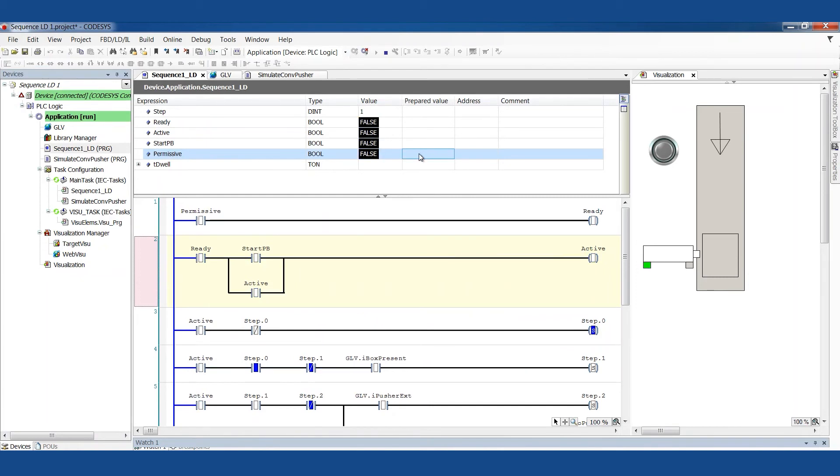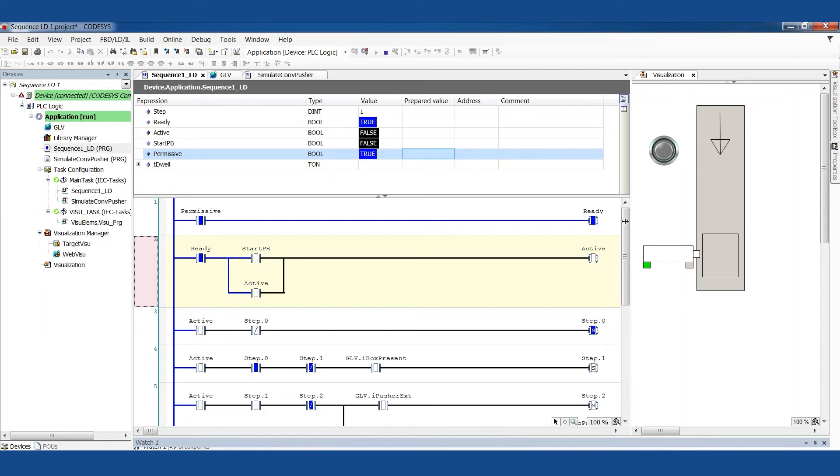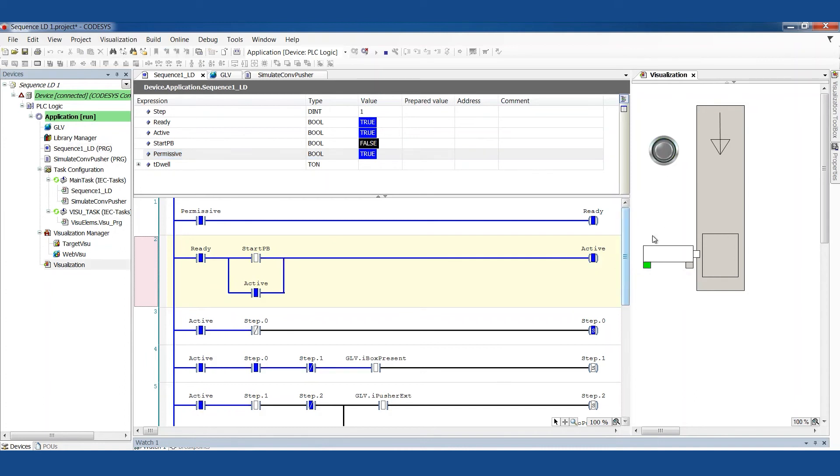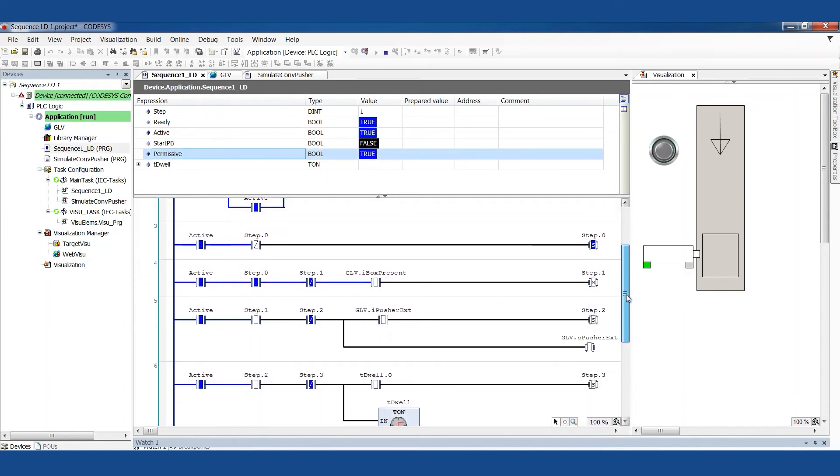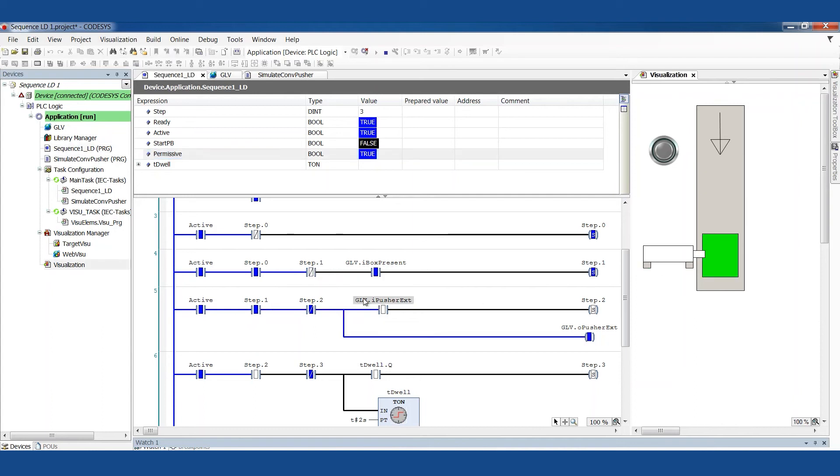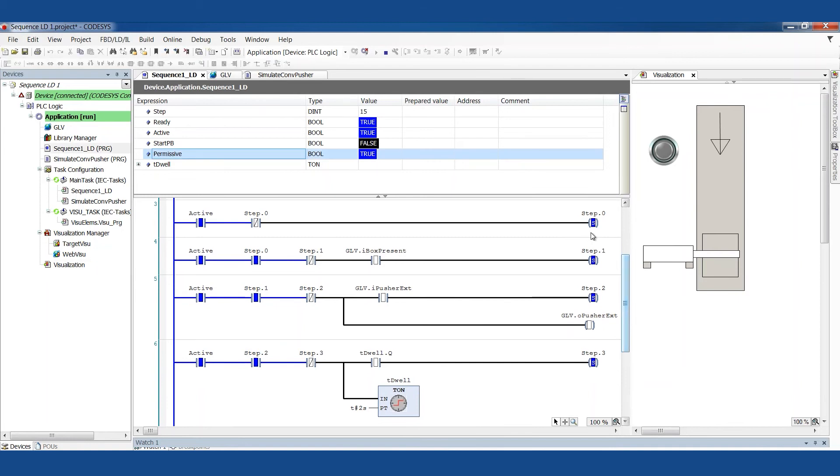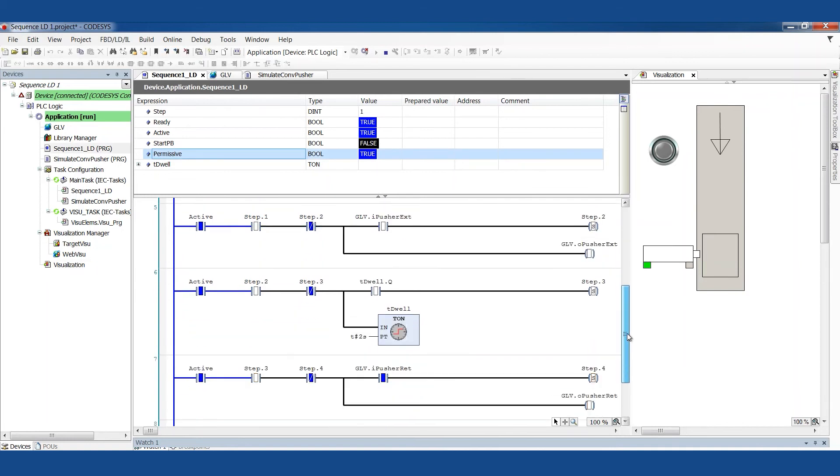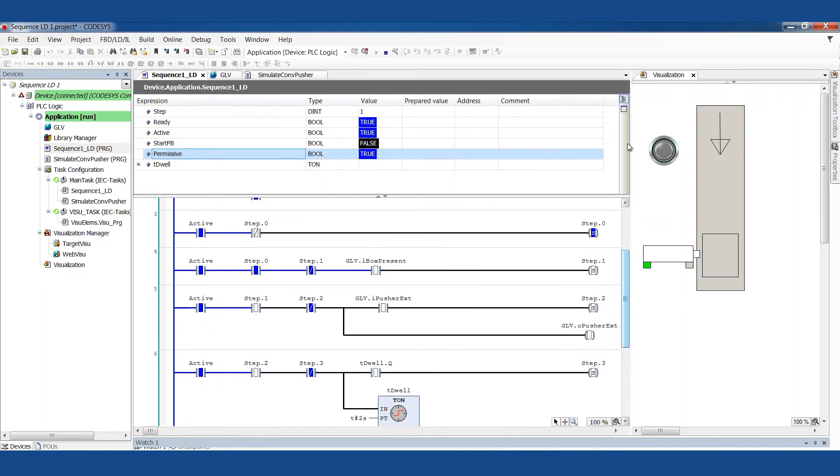I'm going to just reset this whole thing. Set my permissive to true. Again, that's guard doors are closed or e-stops are happy or we're in auto mode or whatever those permissives are. I see we're ready now. It's waiting on me to push the start button and then we'll go to active. We're active now. And now it's waiting for a box. Notice we are in step zero. I'm going to give it a box and then this will be true. So we'll get to step one and then we're going to start pushing. And we're pushing. We got there. Notice how these are lighting up and making a big blue line while they're going down.